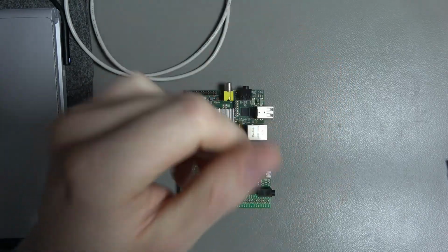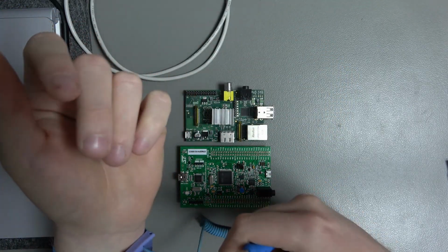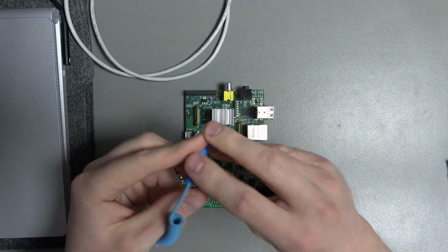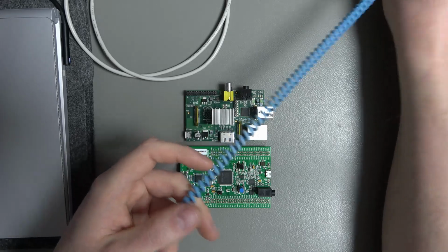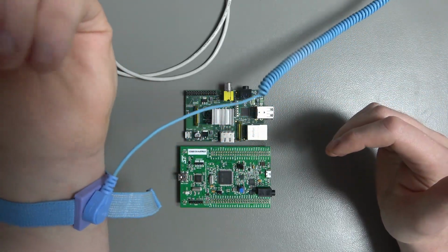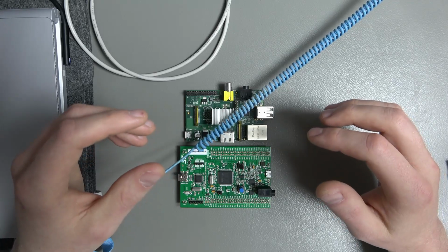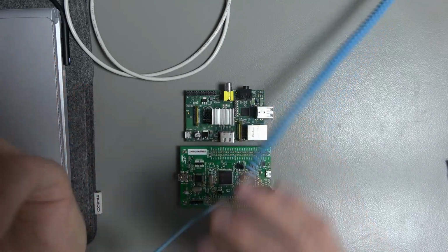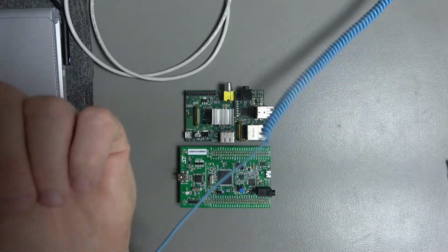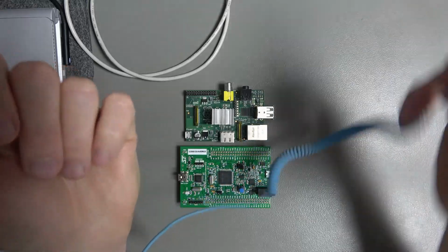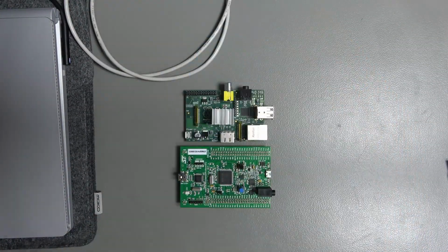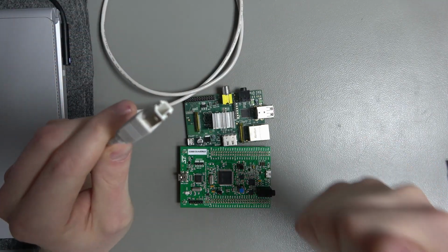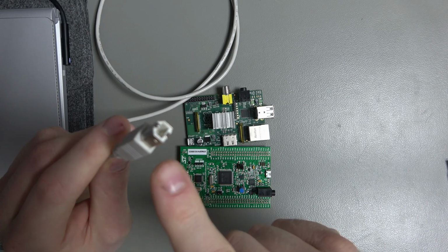Now let's say I work in a sensitive area, an area where expensive hardware could get destroyed, but I ground myself using an anti-static wrist strap. I have a laboratory power supply here, I plug the earth connector in, and now I'm on the safe side because I'm earthed, right? Wrong. This earthing doesn't help in this case. If anything, it only makes things worse, because it potentially lowers my impedance to earth. We're not talking about electrostatic charges here, which is where this anti-static wrist strap would help, but a voltage to earth. This means that the better earthed I am, the more dangerous this voltage to my hardware becomes.